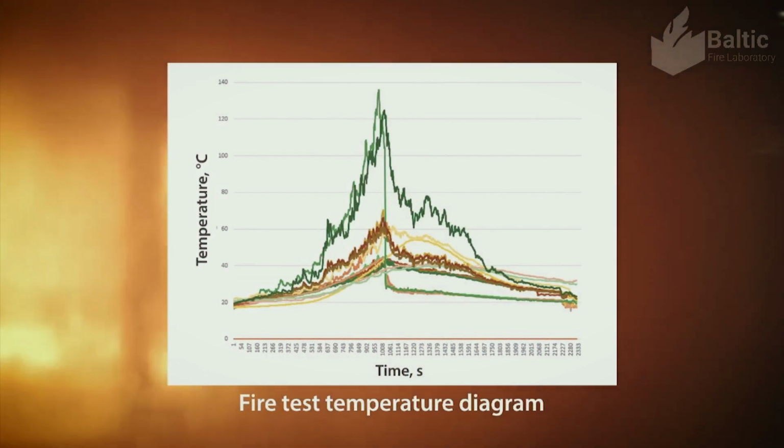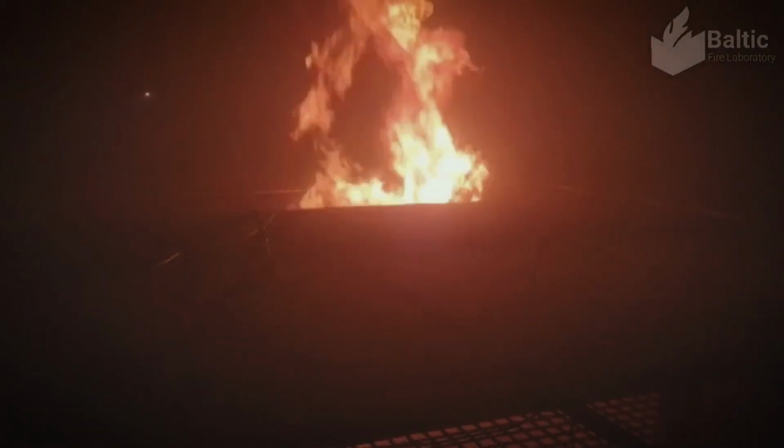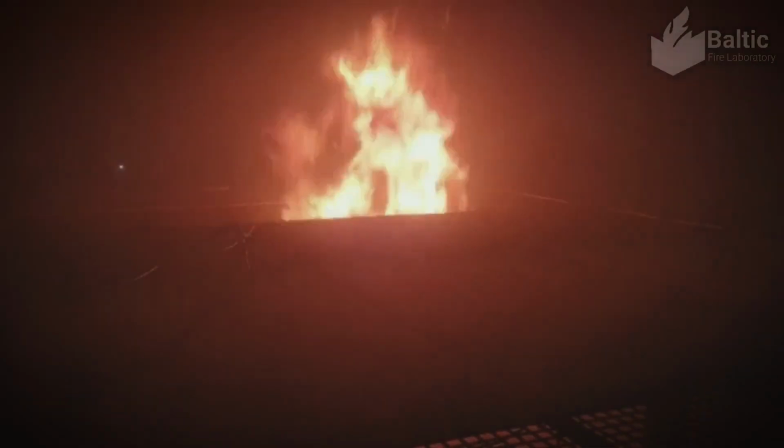It means that this ventilation is cooling the bulb which is installed in the sprinkler nozzles in the water mist nozzle. So where we had a 68 Celsius bulb, we got activation when the thermocouple close to the nozzle was at 125 Celsius, 2 times more. So now you can imagine how difficult it is to activate the system in the fire test.